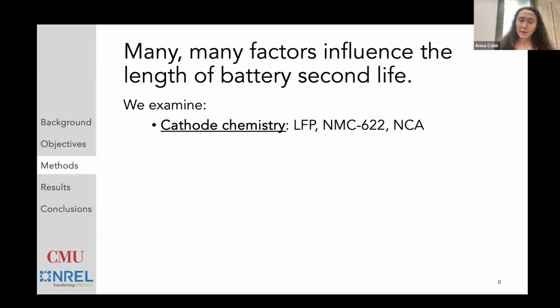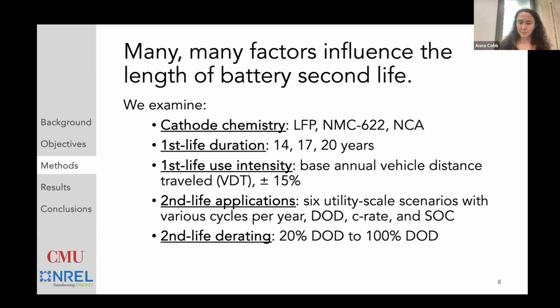There are many factors influencing how long batteries last in second life: the cathode chemistry, how long the battery spends in first life, and how intensely it's used in first life, measured as vehicle distance traveled as a function of vehicle age from National Household Travel Survey data, varied plus or minus 15% to set our bounds. We also look at six different second life applications varying across several characteristics, and at the derating factor—oversizing the system so a 100% depth of discharge cycle becomes smaller. We examine derating factors from 1 to 5, where a factor of 5 turns a 100% depth of discharge cycle into a 20% depth of discharge cycle.